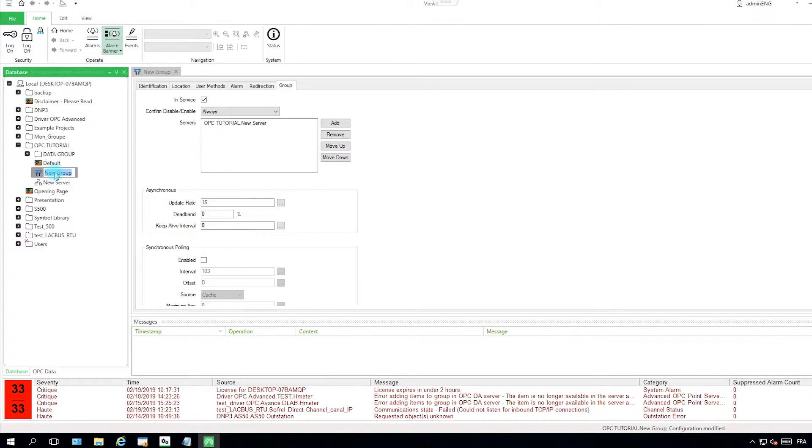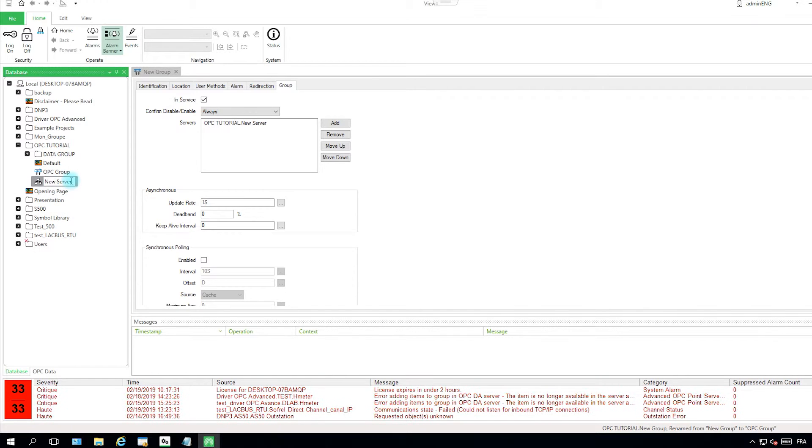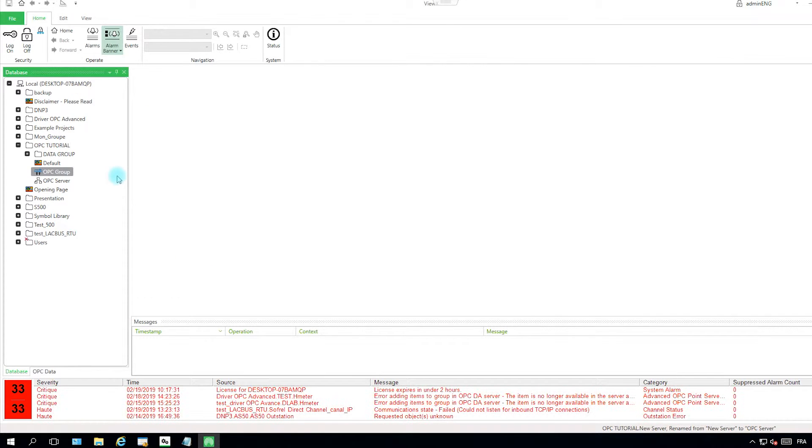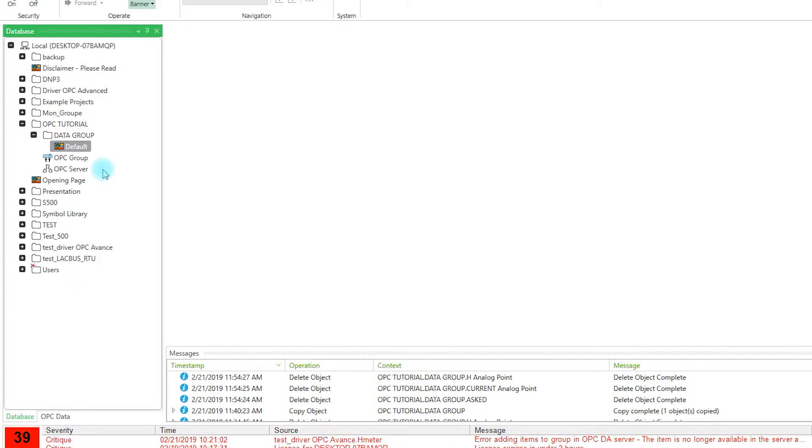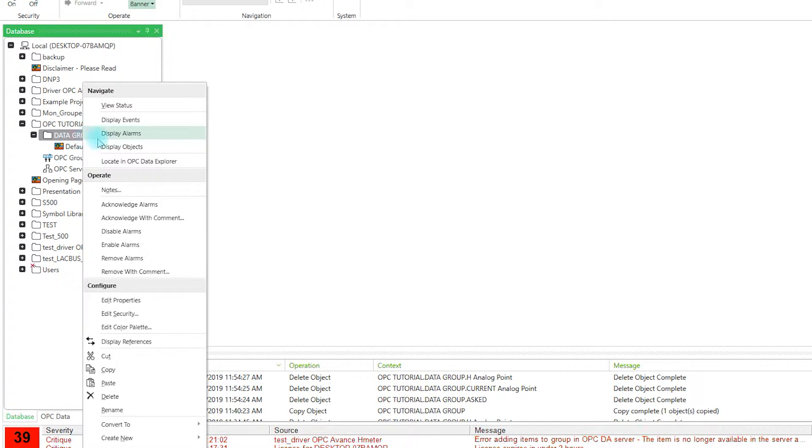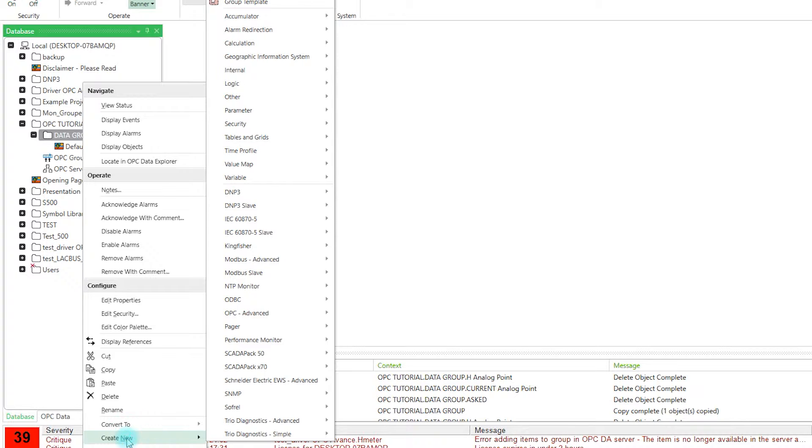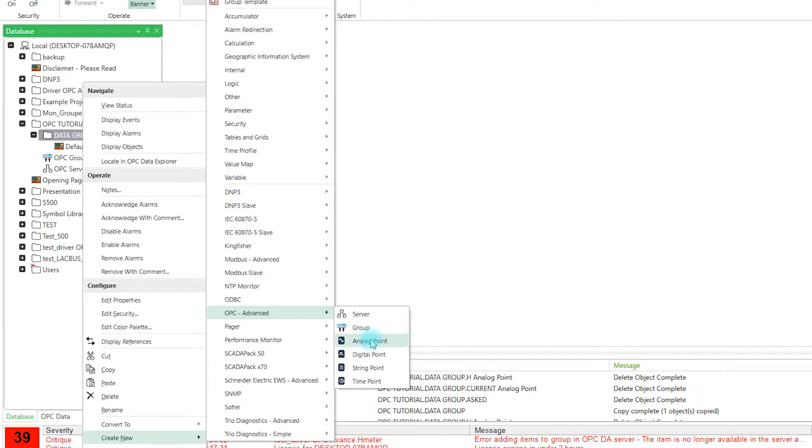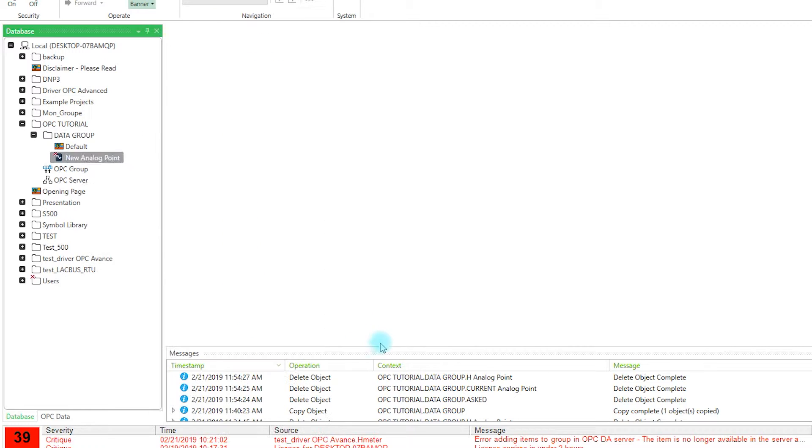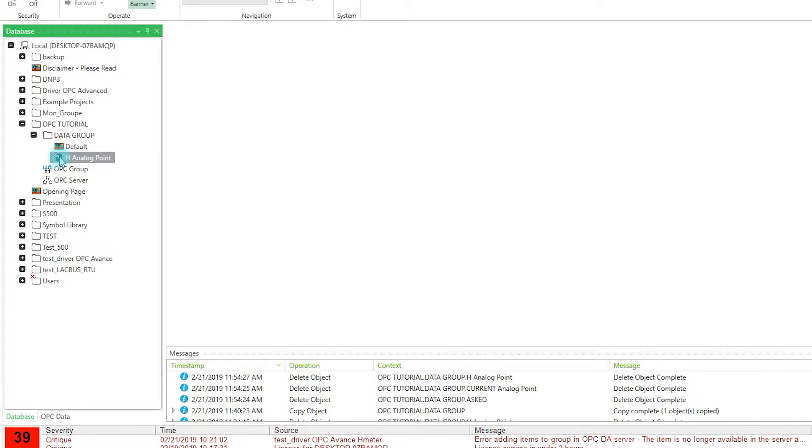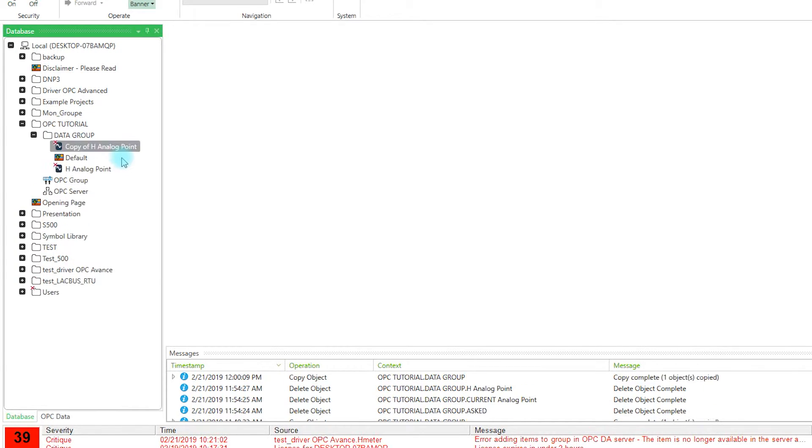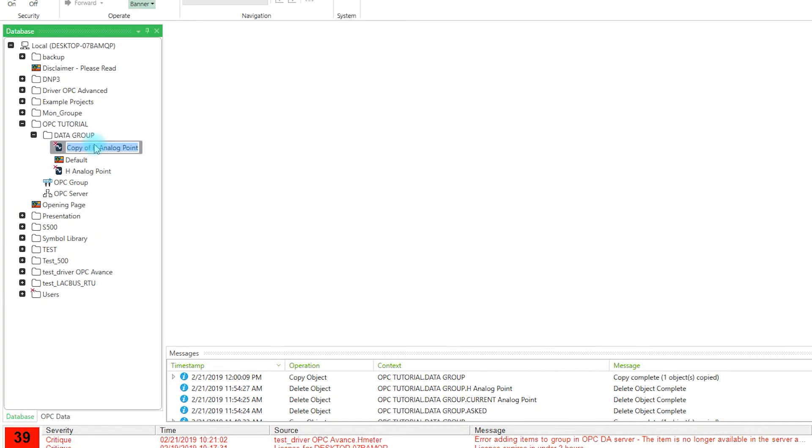I will rename those two items. So now that we have the group and the server well configured, what we have to do now is to create the data. So in the data group we do a create new, OPC advanced, and an analog point. We will create an analog point for the historics and another analog point for the current value.